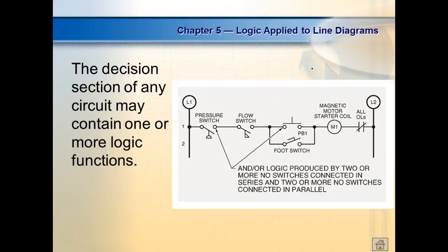You can combine logic. So these contacts right here, watch this symbol: pressure switch, flow switch, these are hooked in AND. These are hooked in OR. So you can have different logic in the same rung.